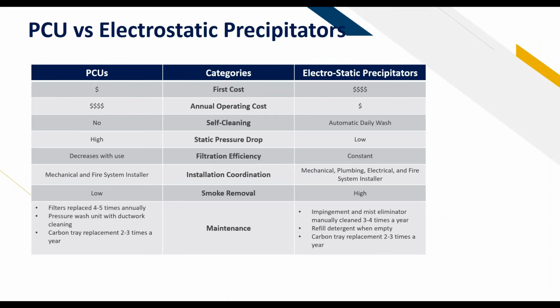So just a quick little breakdown of the differences here. The PCU's first cost is going to be lower than the electrostatic precipitators, but the annual operating cost is going to be much higher in that pollution control unit. And that mostly comes down to the filter replacements. It can be quite costly because you have to do it about 4 to 5 times a year. It really just comes down to maintenance, but this has an automatic daily wash. It is more of a high-end system. So if you want to have that high-end system, the ESP is more robust.